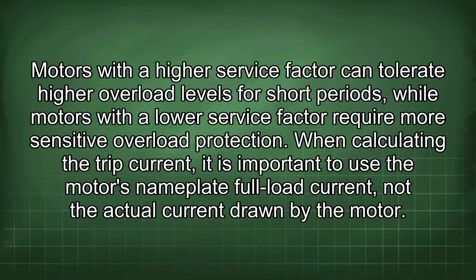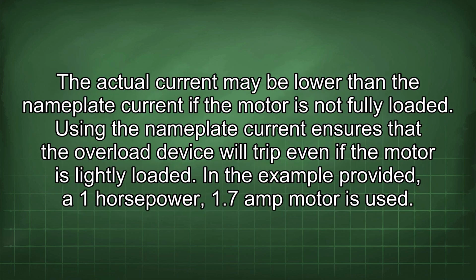Motors with a higher service factor can tolerate higher overload levels for short periods, while motors with a low service factor require more sensitive overload protection. When calculating the trip current, it is important to use the motor's nameplate full load current, not the actual current drawn by the motor. The actual current may be lower than the nameplate current if the motor is not fully loaded. Using the nameplate current ensures that the overload device will trip even if the motor is lightly loaded.